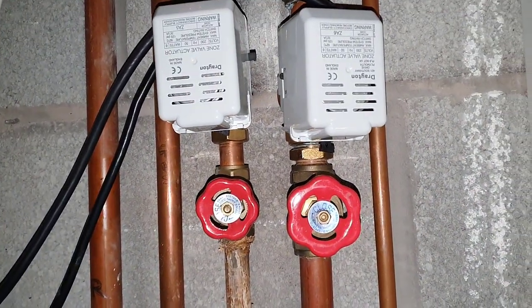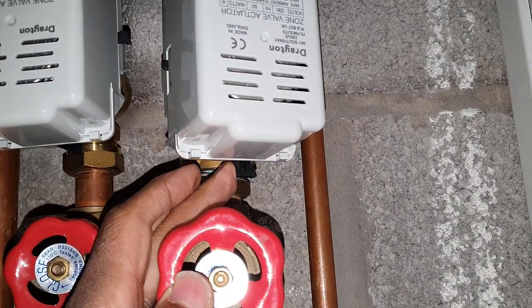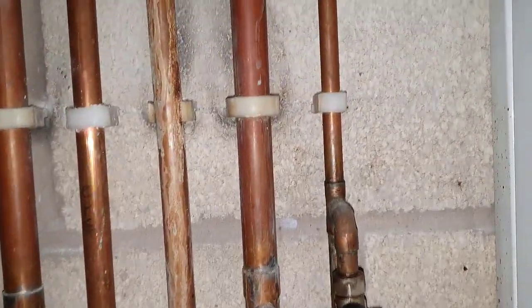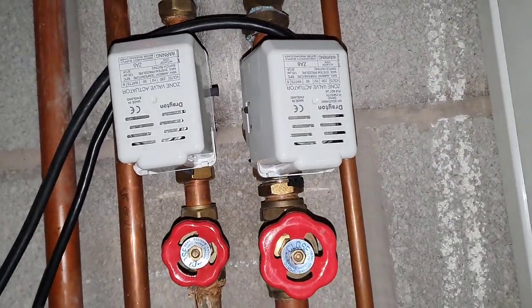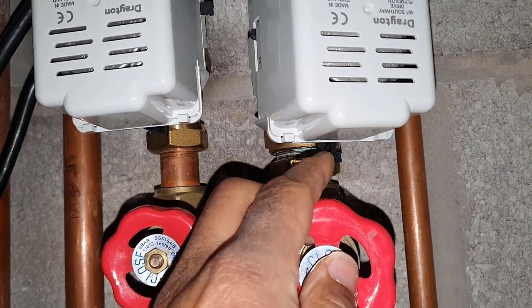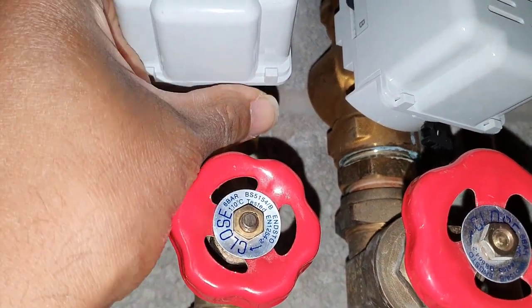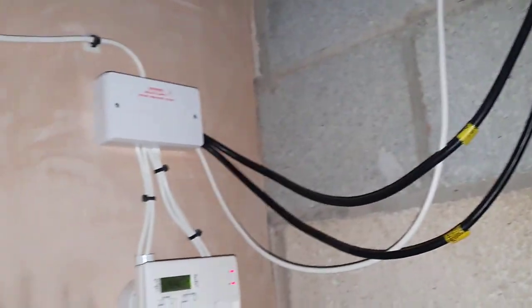I noticed the lever on this one is down. Let's see if it moves across — yes, it's moving across like that. This is 28mm pipework, so that's likely for the heating. Then the one next door — if you look in comparison you can see that one's down a lot, this one's jammed up, and if you look more closely I think it's stuck behind the tab as well. So that's not going to help. Let's see if we can release it — it's really jammed, not moving.